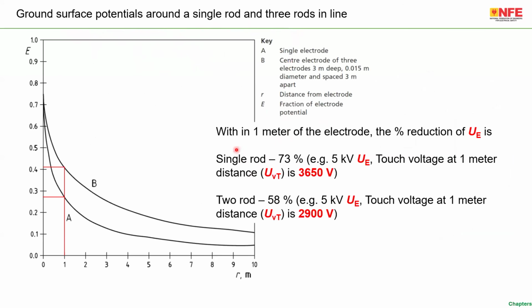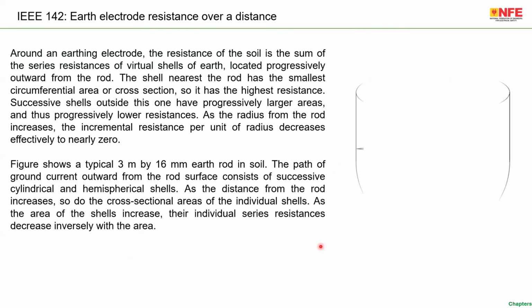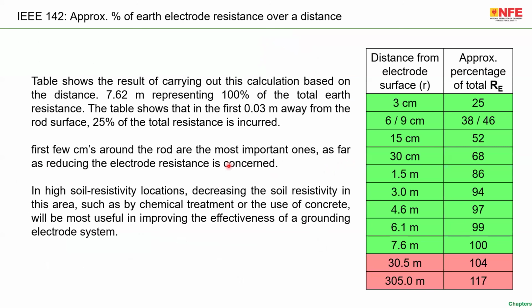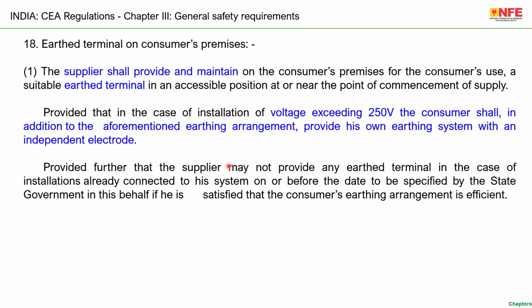With almost the same method, if we calculate or simulate, for example, if you have a single earth electrode where UE is 5 kV, meaning IE times RE is 5 kV, the touch voltage is something about 3650 volt. If you have 3 earth electrodes, then it's 2900 volt and so on. So please look at IEEE 142 and calculate it.